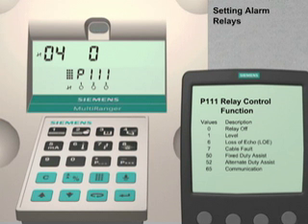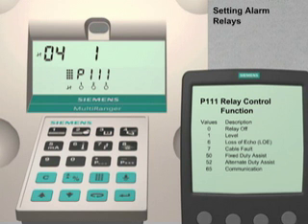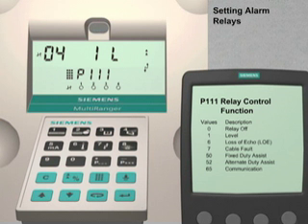This means that relay number 4 is currently turned off. We will set relay number 4 to be our high level alarm. The programming chart shows that a general level control function with a numeric value of 1 can be used to provide relay control based on the liquid level in the vessel. Enter 1 followed by the enter key to assign this function to relay number 4. To set relay number 4 to be a high level alarm, press the units key. The Multiranger will display a double up arrow. Press the up arrow key three times. The Multiranger will now also show a single letter H for the high level alarm. Press the enter key. Relay number 4 is now our high level alarm relay.